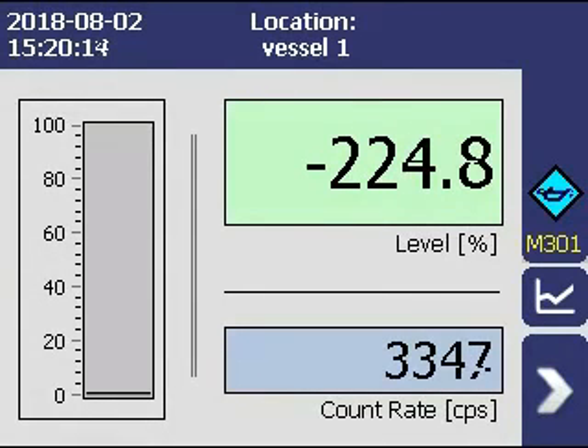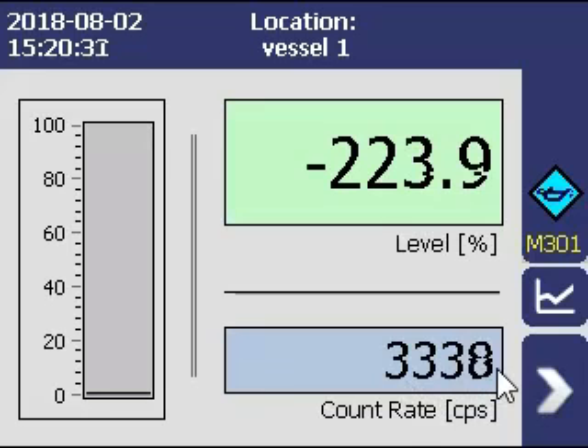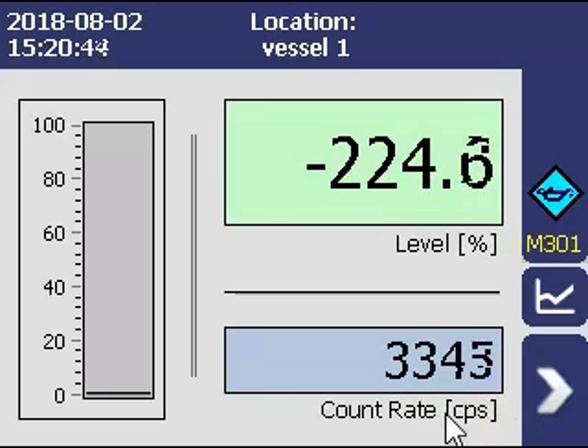Berthold LB470 setup and calibration. The installation is complete, the shutter is in the open position, and the system is powered up. If you notice the count rate field on the home screen is displaying 0 on your gauge, ensure that the plus or positive terminal in the cabinet is connected to the number 1 terminal in the detector, and that the minus or negative terminal in the cabinet is connected to the number 2 terminal in the detector. If this is all correct, please contact Berthold Service for help diagnosing the issue.